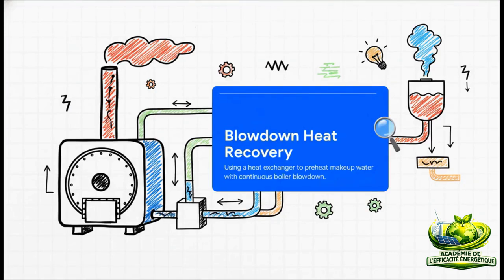So, to stop dissolved solids from building up and wrecking your system, boilers do what's called a blowdown to purge some of that water. But here's the catch: that water is highly pressurized and incredibly hot. If you're just dumping it, you're dumping money. Continuous blowdown heat recovery fixes this. It uses a heat exchanger or a flash tank to capture that discarded thermal energy, and then reuses it to preheat your ice-cold incoming makeup water. If your boiler has a continuous blowdown rate of more than 5% of its total steam rate, you are a prime candidate for this upgrade.